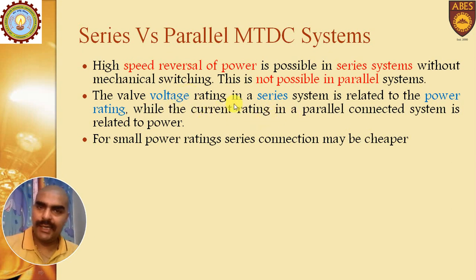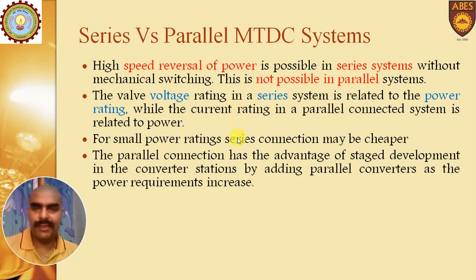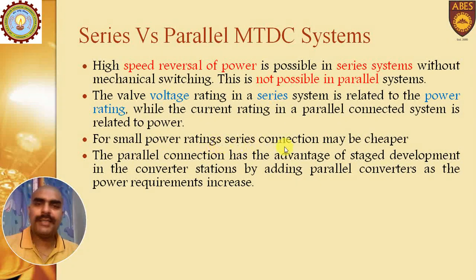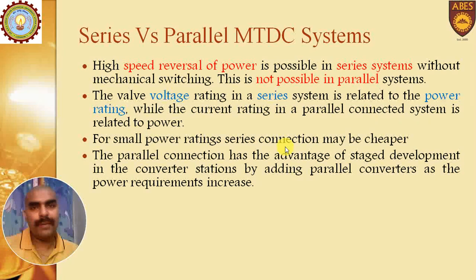Accordingly, voltage and current ratings are related to power in the respective MTDC systems. For small power rating, series connection may be cheaper, but parallel MTDC may be more cost-effective overall. The parallel connection has the advantage of stage development in converter stations by adding parallel converters as power requirements increase in phases.